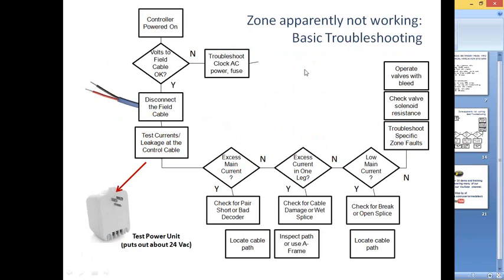Here's a little troubleshooting diagram that we use when we do the training on two wires, just to give you an idea of the things that you start out doing. And as like I said, start with the controller, because you're going from the source of the power toward the field application. So making sure the power is okay, things are coming out of the controller okay, the controller thinks everything's fine, or you know, it's working at least. And you get down to where you're troubleshooting the field cable. And there's a little picture there that shows that test power unit that I mentioned. You may need to carry a big extension cord in order to get power to this little unit, unless you've got some other 24-volt AC signal generator. But it's worthwhile because you can put your own signal on there that's very easy to measure, and the controller doesn't have to be working. It can be dead, it can be unhappy, it can be disconnected for safety, whatever.